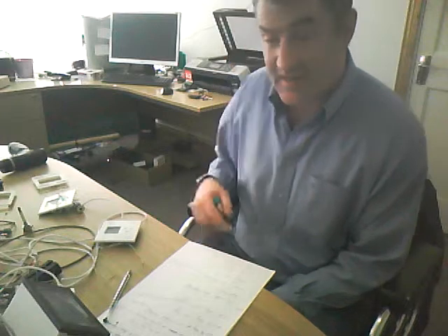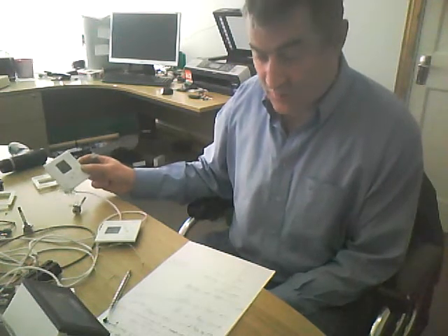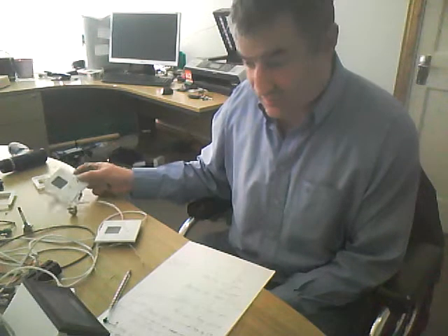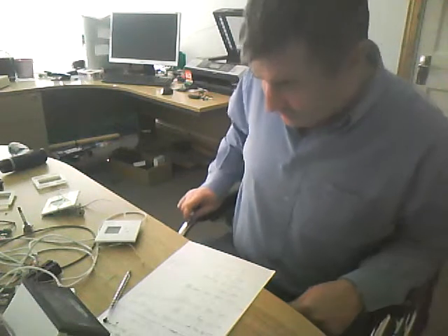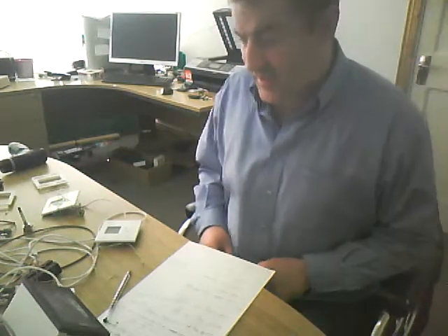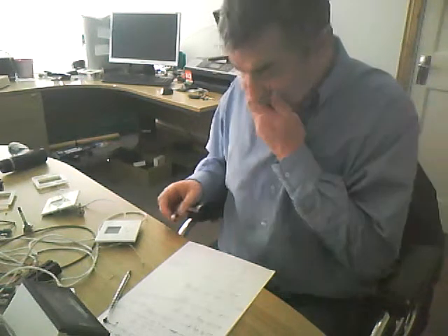So your source is an auxiliary sensor and your IDX is 1. That's when we're this guy over here. We set it up as an SR1 and a serial number 1. So that's where your IDX1 is out of. And then you set your high and your low limits around which the differential will work. So the high we have set as 10 and the low is 5.